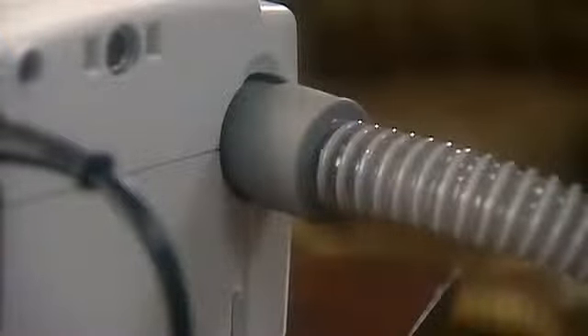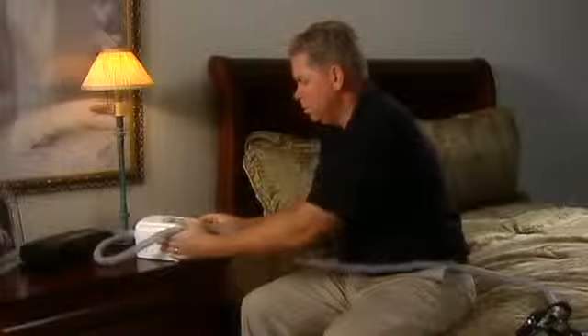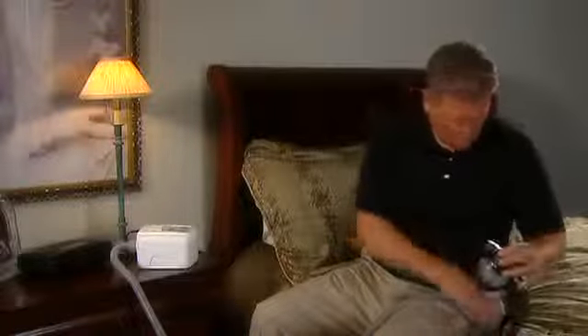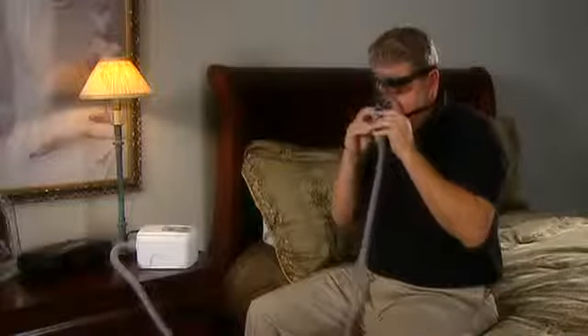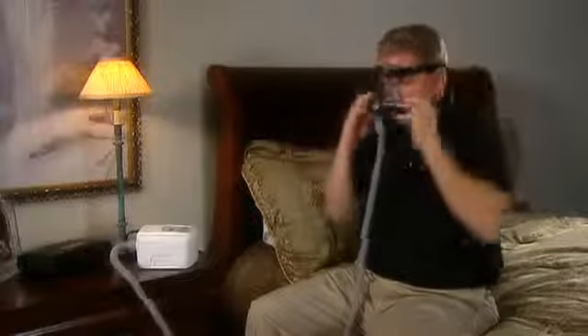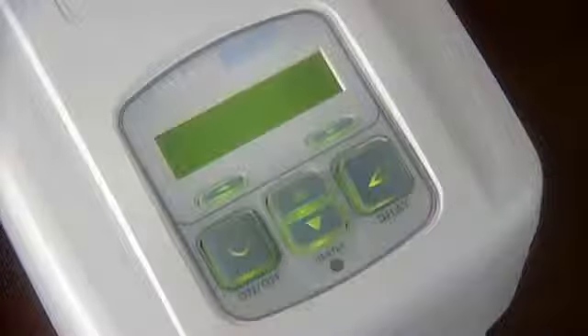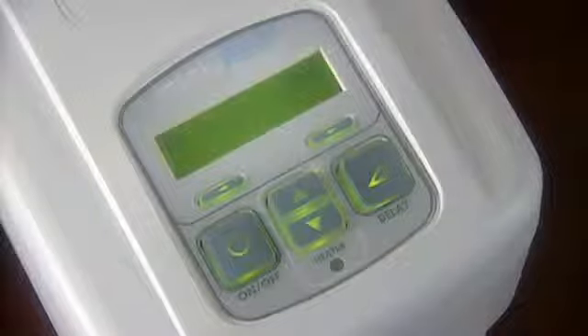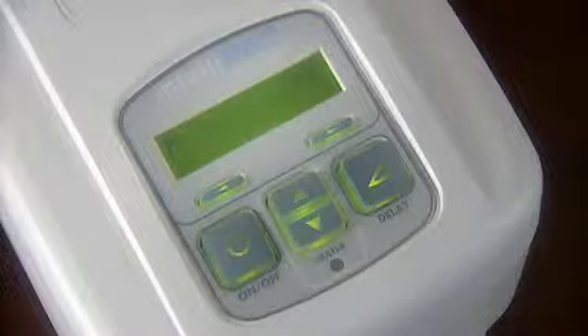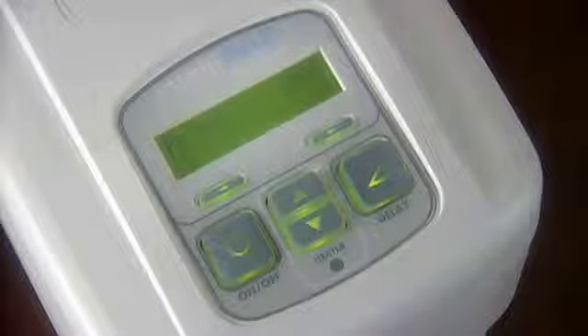Next, attach the air supply tubing to the air supply interface, as shown here. This tubing is specially designed to prevent kinking and permit uninterrupted airflow. Use only the tubing that is supplied with your DeVilbiss device or air supply tubing recommended by your home care provider. Prepare the mask by referring to its instruction guide, then connect the air supply tubing to the mask. To begin operation, put on your CPAP mask and press the on-off button on the keypad to turn on the airflow. Your device may also have been enabled by your home care provider to start airflow automatically by taking a few breaths through the mask without having to press the on-off button.